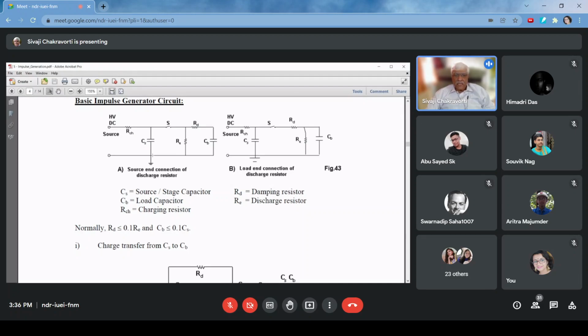When CS is charged, one terminal of CS has to be earthed. Never operate a high voltage system without proper earthing. Then there are two resistances: the series resistance is called the damping resistance, and the parallel resistance is called the discharge resistance. The discharge resistance is used because both capacitors discharge through it. I will explain why the series resistance is called the damping resistance.